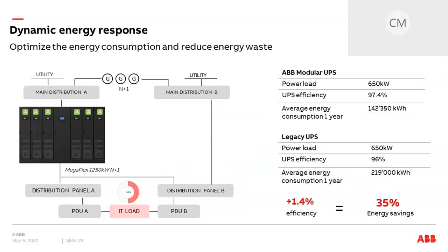On the left side, we have a power distribution topology tier 3 for a 1.25 megawatt load with N+1 redundancy. On the right side, we have an example with two UPSs working at a power load condition of 50%, with an efficiency of 97.4%, versus a legacy UPS with 96%. Over a year, this efficiency difference of 1.4% represents up to 35% energy savings. This is in the case when the IT load is constantly low at 50%.